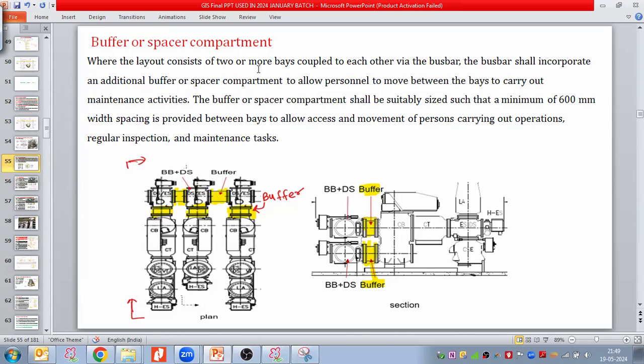Where the layout consists of two or more bays coupled to each other via the bus bar, the bus bar shall incorporate an additional buffer or spacer compartment to allow the maintenance person to move between the bays to carry out maintenance activity. The buffer or spacer compartment shall be suitably sized such that a minimum 600 mm width spacing is provided between bays to allow access and movement of persons to carry out operations, regular inspection, and maintenance tasks in the module. So this is the concept; how does it come into the drawing?